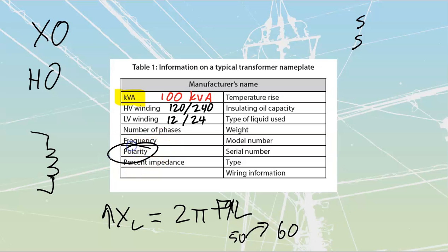Polarity is going to be a different thing than what we're used to. We're going to cover what transformer polarity is in the next one, but each transformer is going to be either additive or subtractive, and it just refers to an instantaneous value. We will look at that later on. It could be written as additive or subtractive, or a plus or a minus.